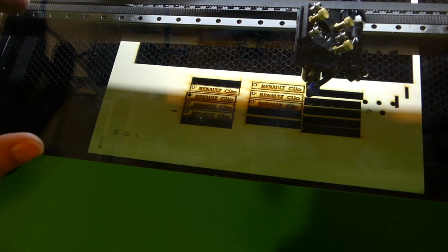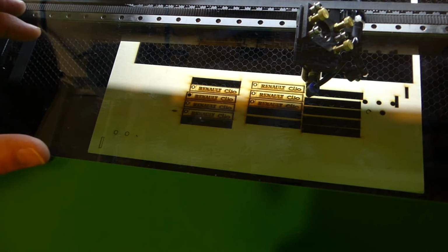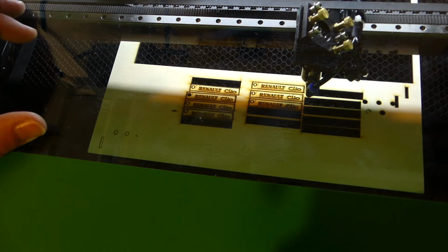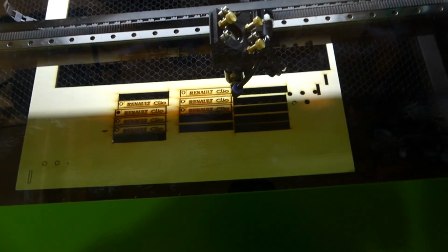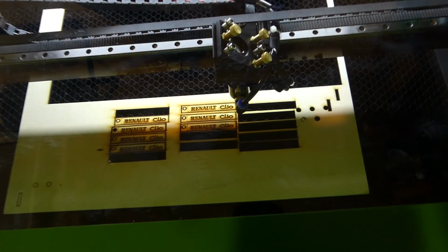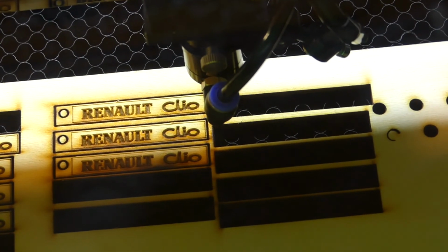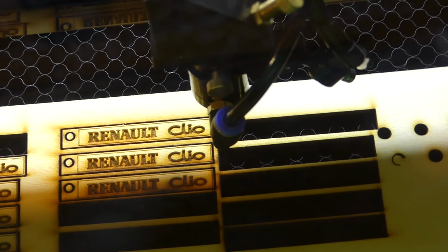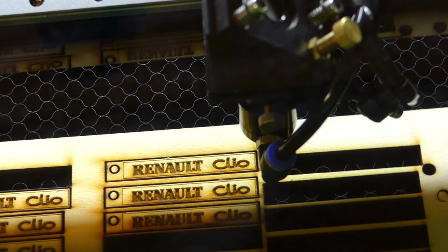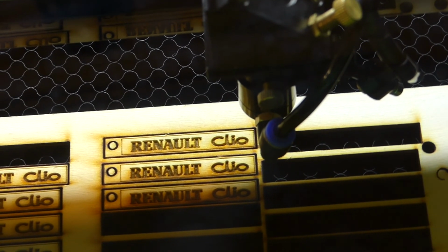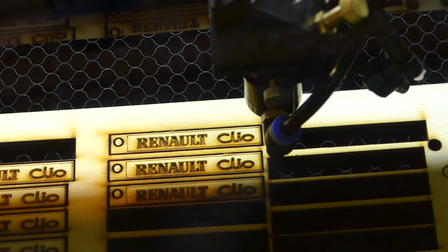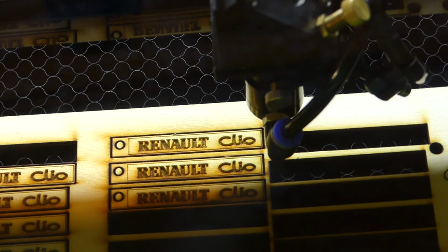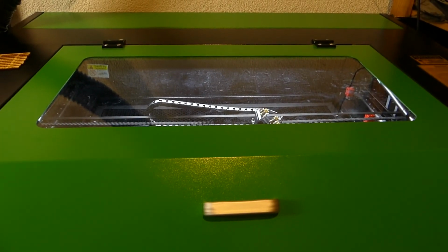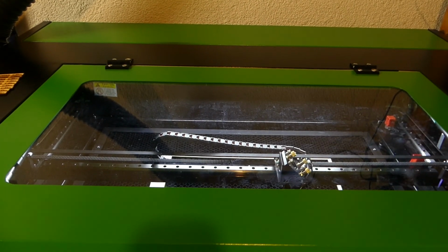I don't know. And I checked all of my mirrors, they're all clean. The optics are also clean. I did find a little bit of debris in the laser head, in the lower lens that is focusing on the outlet, and I'm not sure that debris was there when I started working with it, so could be that I have some more metal shavings or plastic pieces that just found their way into there and got loose. But I've cleaned everything, and now that it's clean, it actually works pretty nice, and I'm happy with it.